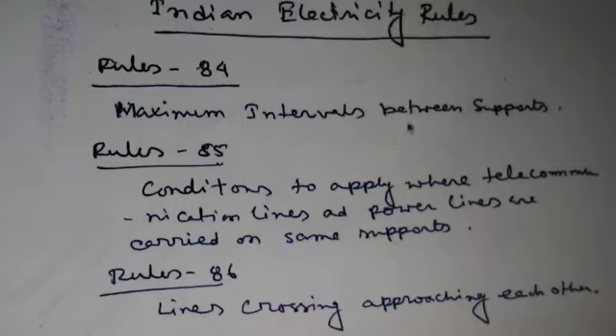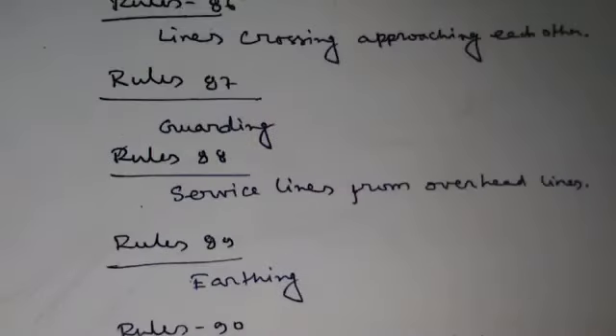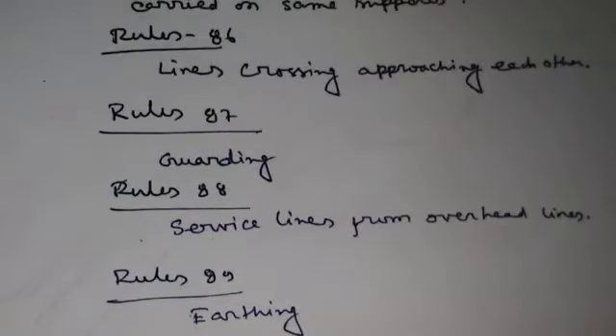Now rule number 86. Rule number 86 is related to lines crossing or approaching each other. This rule is based on the following points. First point, where an overhead line is in proximity to any telecommunication line, the owner of the overhead line shall protect it in a manner laid down in the code of practice of the Power and Telecommunication Coordination Committee.